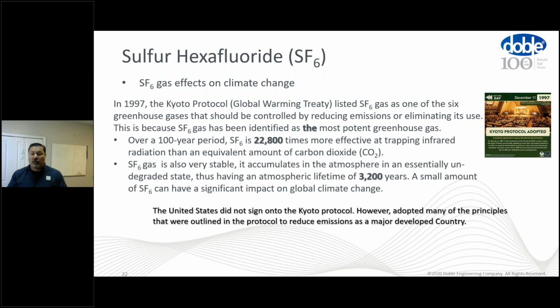Collectively to that effect, it's also very stable, as I mentioned before, because of how SF6 gas works. It would accumulate in the atmosphere, essentially in an undegraded state. So it has a lifetime of over 3,200 years, meaning that even SF6 that possibly Henry Moissan himself created may still be in our atmosphere. So any small amount of SF6 obviously has a major impact on climate change. Be it known that the United States did not sign on to the Kyoto Protocol, but they did adopt a lot of the principles outlined in the protocol to reduce emissions as a major developed country.